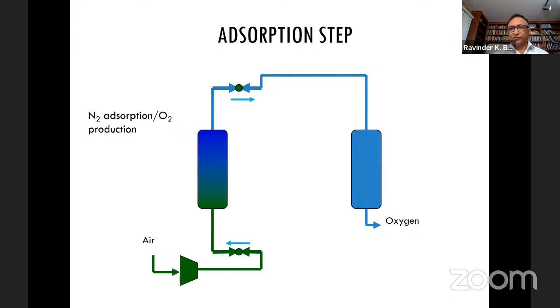And then you have another valve, much smaller, so that you can maintain pressure here. Oxygen is coming out and is going into this receiver, which is then supplied to the user. So that's all for the adsorption step. For the desorption step, you have to add another valve, which we call the waste valve. You close the product valve, you close the feed air valve, and you open the waste valve. All the nitrogen from this will come out through this valve and be wasted. And during this time, the oxygen would be supplied to the user from this receiver tank.